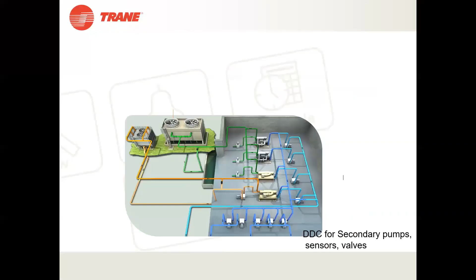Nevertheless, we can always integrate the low side with the CPM. For example, if you have only 2 chillers with 5 AHUs and related VFDs and VAVs, by extending with some DDC controllers for those equipment, we can always put it into the chiller plant manager, and it will give a comprehensive solution. So you need not go for a separate BMS system just for AHU or VAV control.